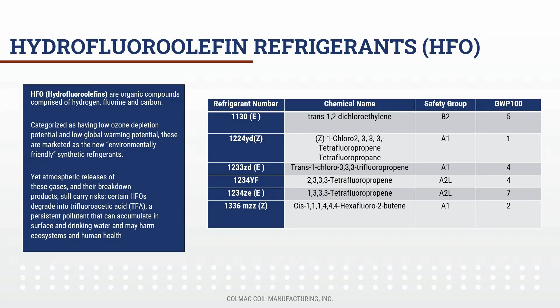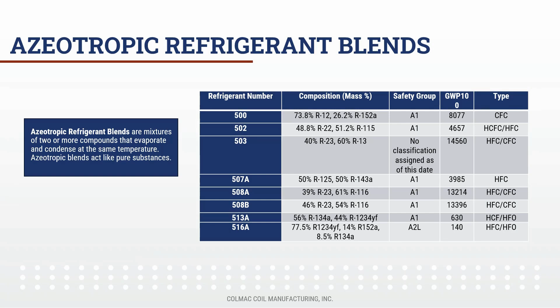Azeotropic refrigerant blends are mixtures of two or more compounds that evaporate and condense at the same temperature. Therefore, azeotropic blends act like pure substances. As previously mentioned, in many applications HFOs do not have the desired characteristics and require compounding with HFCs. One of these is R513A, a blend of R1234YF, which is an HFO, and R134A, which is an HFC.